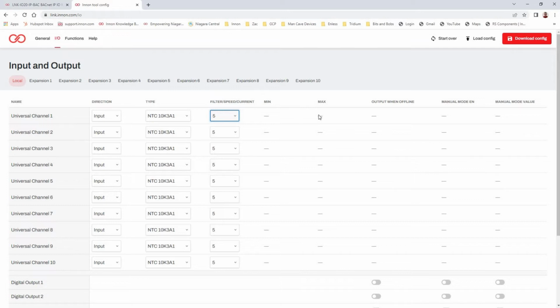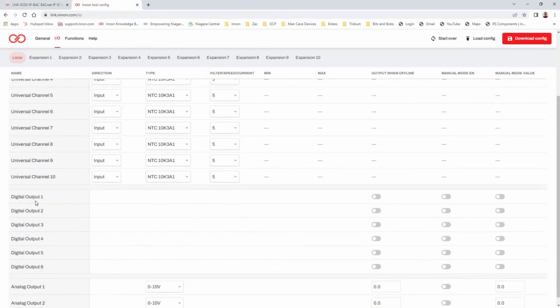So there's some other settings here which are context sensitive. If, for example, we change the output, then you've got some settings here for the watchdog functionality there. So it's all context sensitive. Going down a little bit further, there's the digital outputs. They are just digital outputs, that's all they are, they're on or off. But you can set your watchdog settings here as well. And the manual settings you'll notice down in this column here as well for the outputs. You might want to preset manual settings to give the file to a panel maker and make sure everything's energized so you can prove the relays are coming in properly and things like that. It might save some time. You might want to do that on the pre-commissioning or panel testing stage of your project.